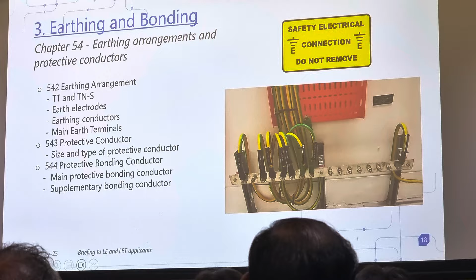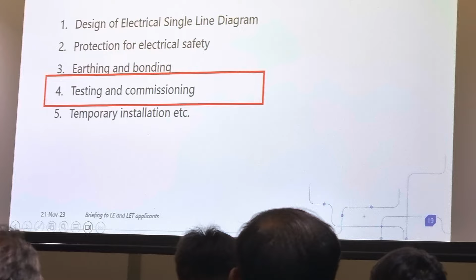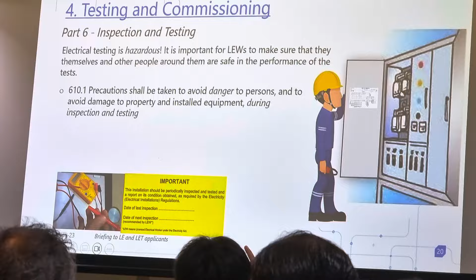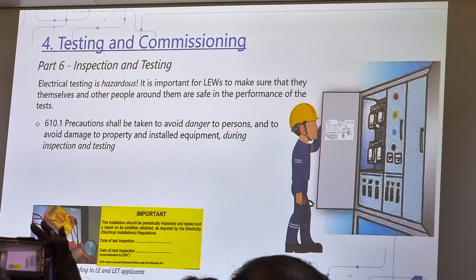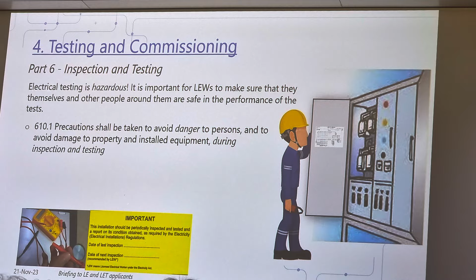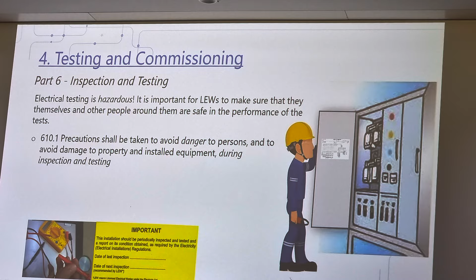Now, once your installation is complete, designed properly, installed properly according to the code, the next important thing is to make sure it's tested properly, because that's the last step before you turn on the supply. Subsequently, you want to go back to regular inspection and regular testing, to make sure that the installation is still safe. Why? Because it's LEW design, right? You want to make sure that it is still safe for operation. How do you know? Again, as I say, you cannot touch it, you cannot feel it, you cannot smell it. What can you do? You can redo testing. You can do some inspection and testing to make sure that the installation is safe.